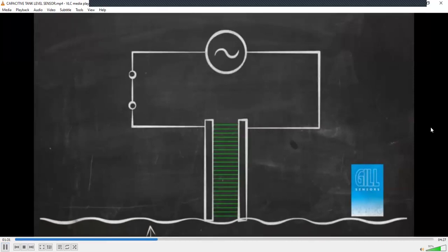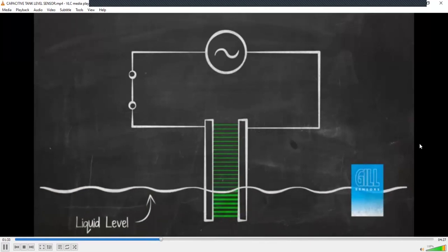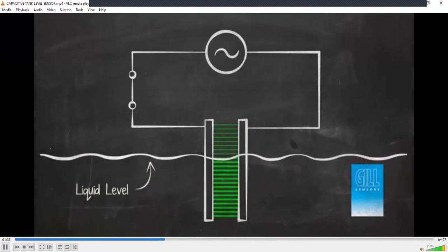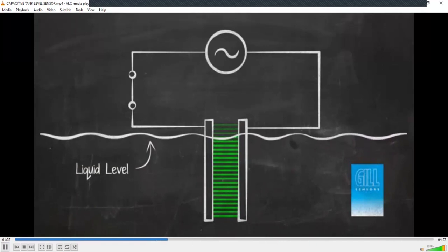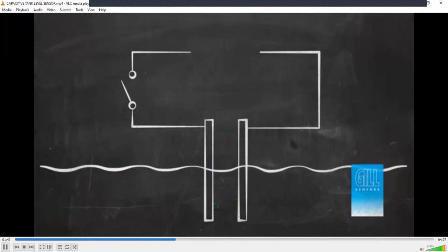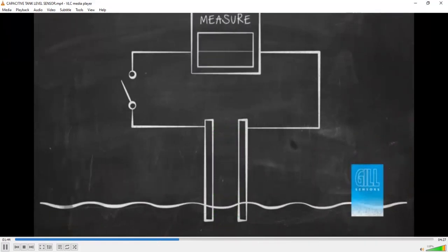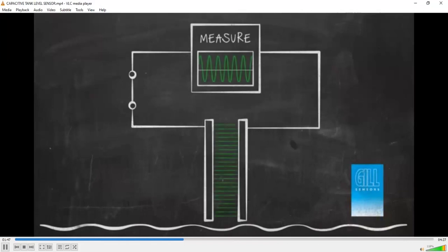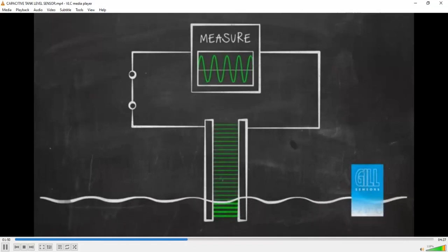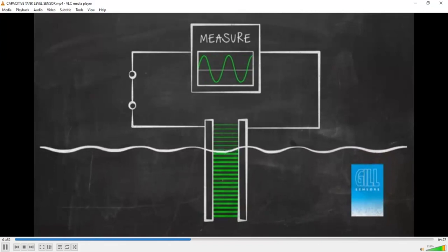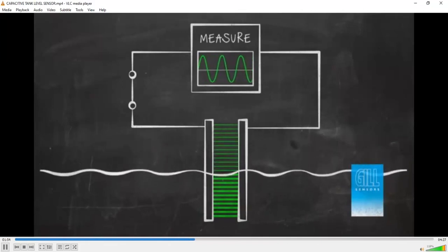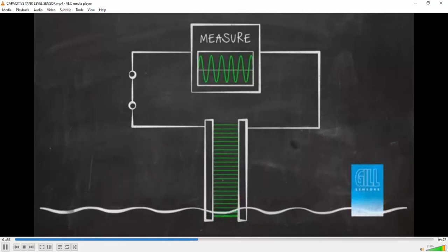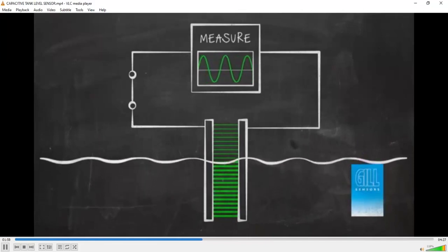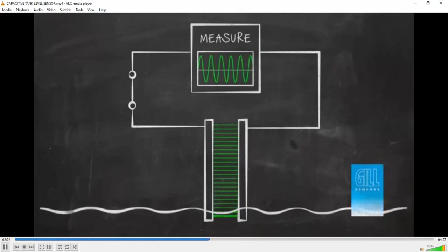As the dielectric liquid is introduced between the electrodes of the capacitor, the capacitance changes progressively and liquid level can be determined. To measure variations in capacitance, electric energy flowing into and out of the electrodes is measured as the circuit potential is varied. A regular flow of energy is established by connecting the electrodes to an alternating current measurement circuit. The more energy flow to the electrodes, the greater the capacitance, meaning more dielectric between the electrodes.